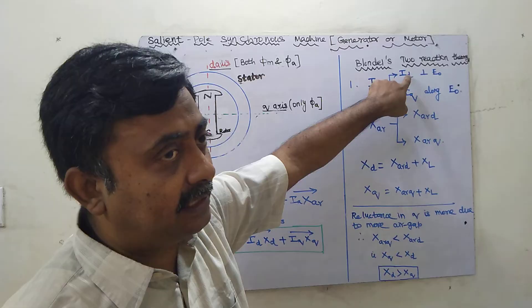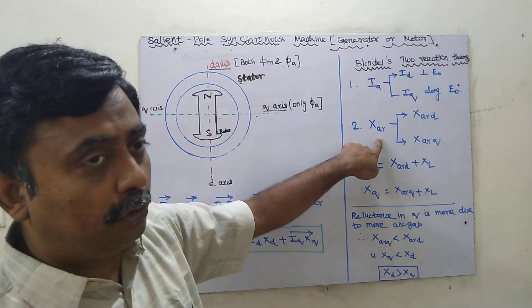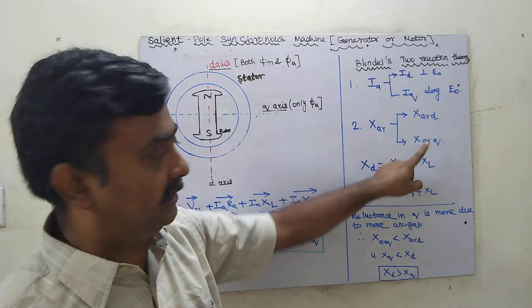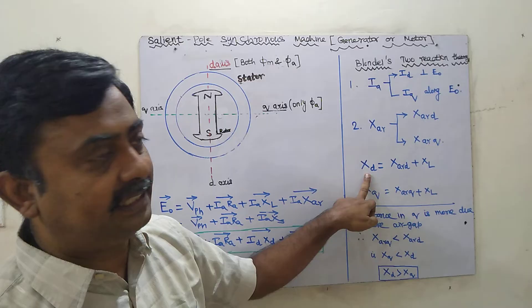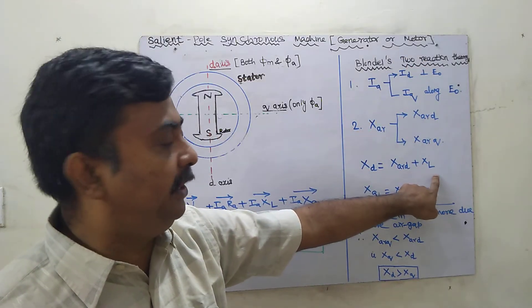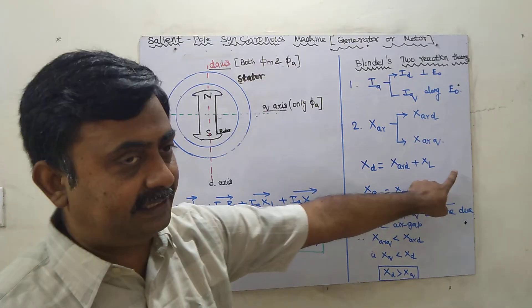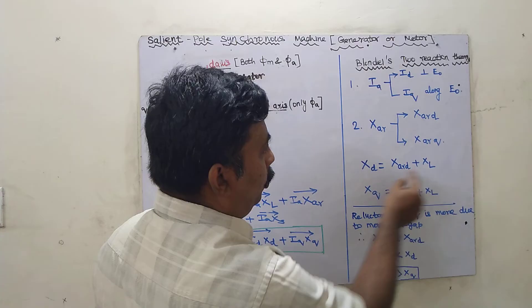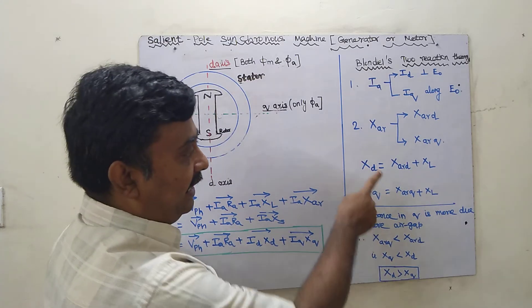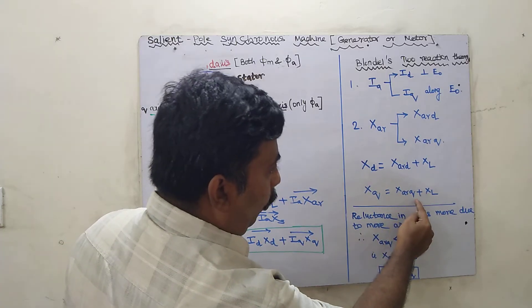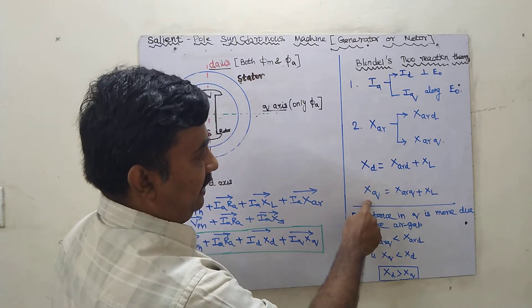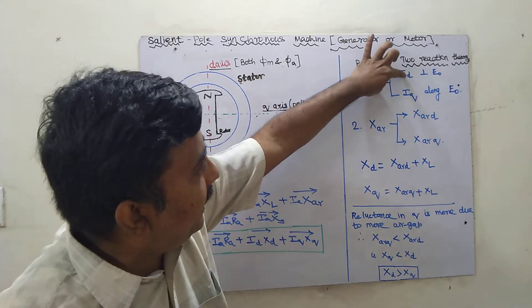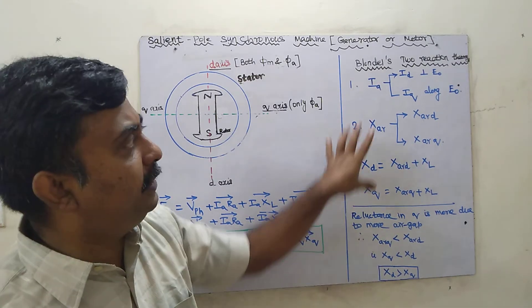The direct axis reactance XD equals XARD plus leakage reactance XL, and the quadrature axis reactance XQ equals XARQ plus XL. So current is divided into ID and IQ, and reactance is divided into XD and XQ. This is Blondel's two-reaction theory. Since the Q-axis air gap is greater, its reluctance is higher and XAR is lower, so XQ is less than XD — that is, XD is always greater than XQ.